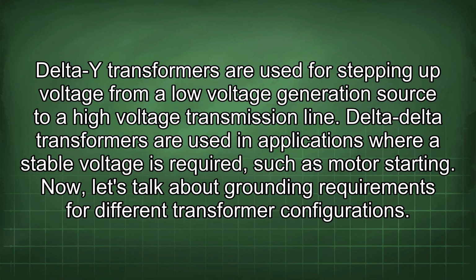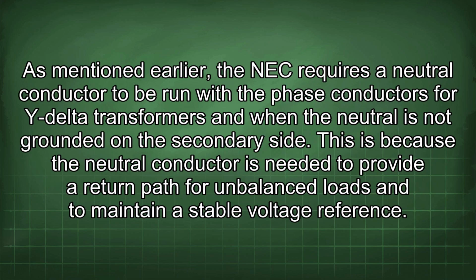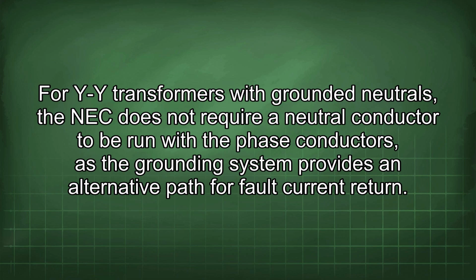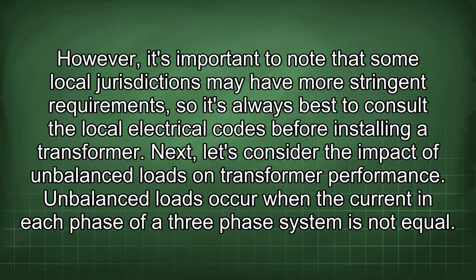Now let's talk about grounding requirements for different transformer configurations. As mentioned earlier, the NEC requires a neutral conductor to be run with the phase conductors for Y-delta transformers and when the neutral is not grounded on the secondary side. This is because the neutral conductor is needed to provide a return path for imbalanced loads and to maintain a stable voltage reference. For Y-Y transformers with grounded neutrals, the NEC does not require a neutral conductor to be run with the phase conductors, as the grounding system provides an alternative path for fault current return. However, it's important to note that some local jurisdictions may have more stringent requirements, so it's always best to consult the local electrical codes before installing a transformer.